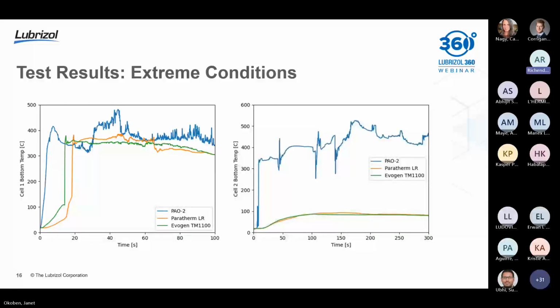But this is an important aspect of what helps prevent that heat from distributing across the module so rapidly. It's that additional heat transfer you're getting out of these high-performing fluids that is ultimately preventing this propagation of thermal runaway. Now if we go to the second cell, this is the one that really matters most. The first cell we knew was going to go into thermal runaway; the second cell is the one with the question mark. For the PAO2 base oil, you see this one also skyrockets to about 400 Celsius and holds steady, a good indication that the heat from the first cell passed to the second cell and caused it to break down and enter thermal runaway.